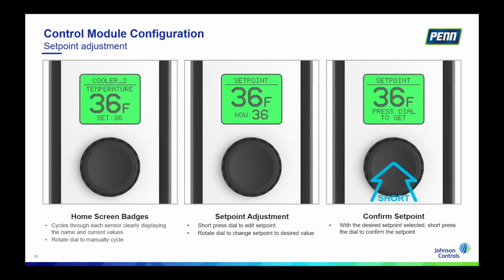So in the middle here, what we've added is these quick access menus. When the badge is showing the set point, you simply push and release the rotary encoder dial, and then you can rotate left or right to increase or decrease the set point. Once you have decided where you want the set point to be, you can then confirm it with that short press and release. This is a big difference from some of the other control systems we have, where something as frequently visited as a set point adjustment is now readily available in these quick access dials.